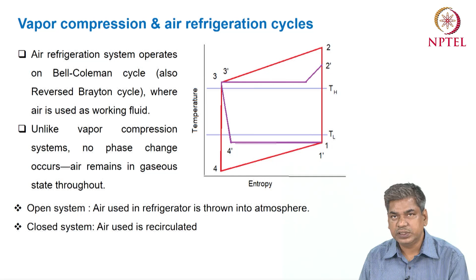But in case of a closed system, the air is recirculated. So when the air is recirculated, this system is just like a vapor compression system, and the vapor compression cycle is also a closed cycle. For that case, if you compare in terms of COP, the vapor compression system has a much higher COP as compared to the closed Brayton cycle. But in some cases, as air is the working fluid for the Bell-Coleman cycle or air refrigeration cycle, the open type cycle is widely used for some applications like air conditioning systems. We can use the open type Bell-Coleman cycle or reverse Brayton cycle.